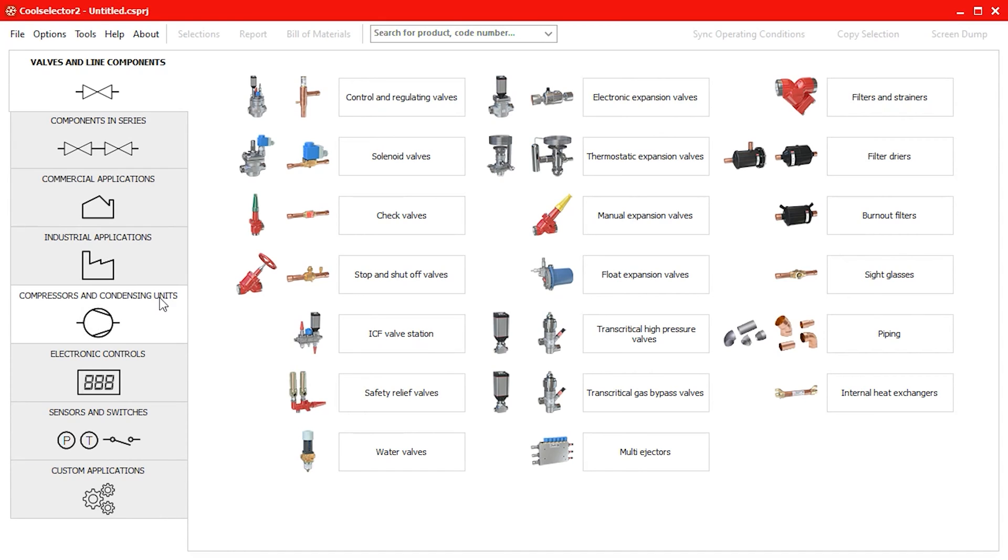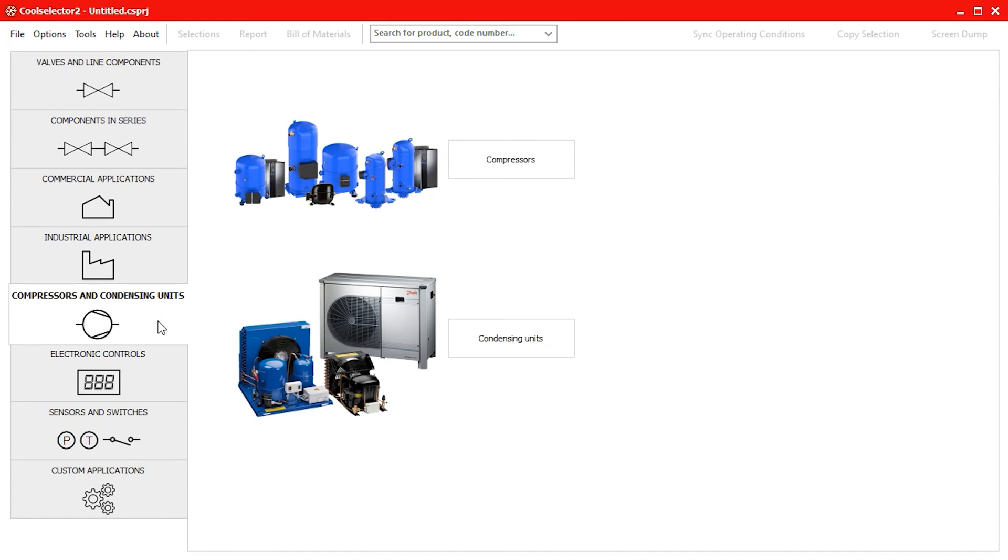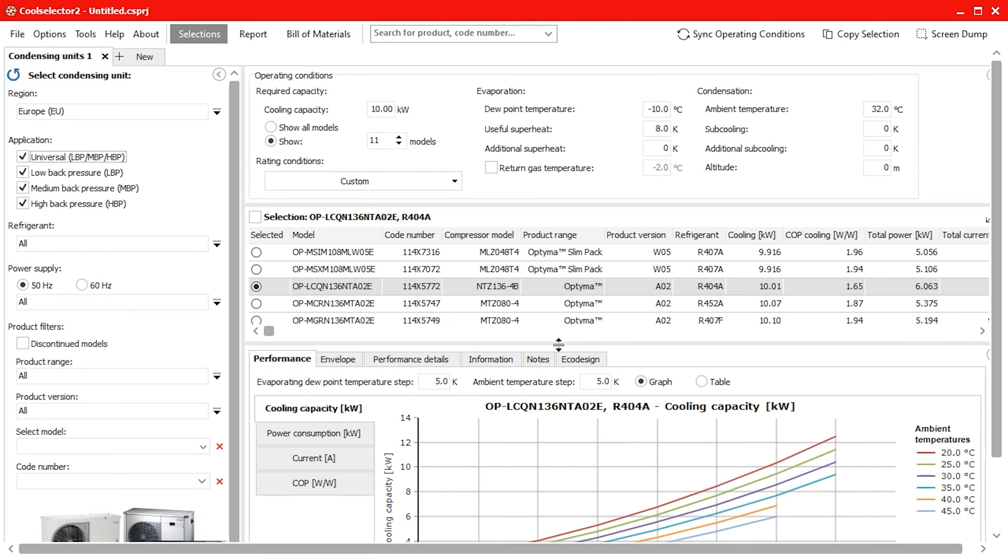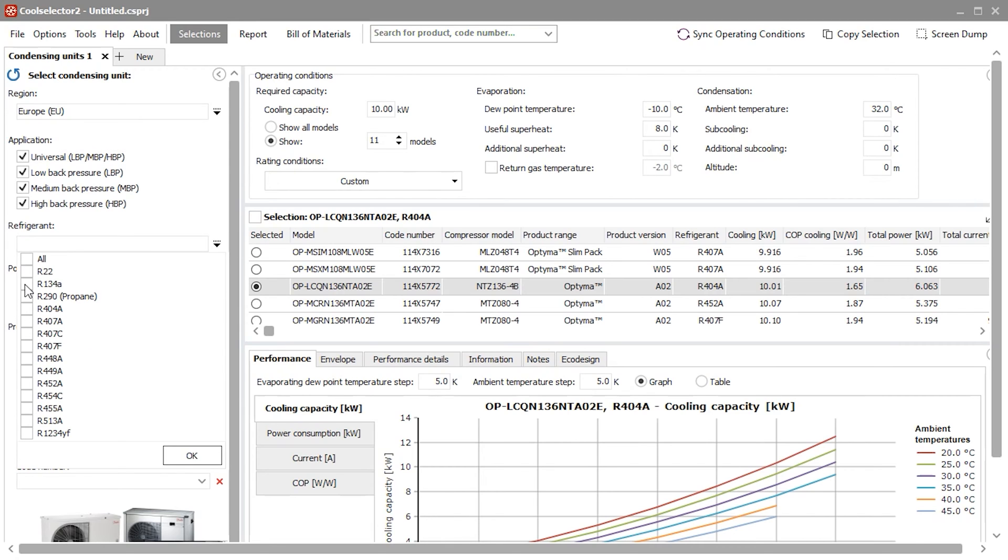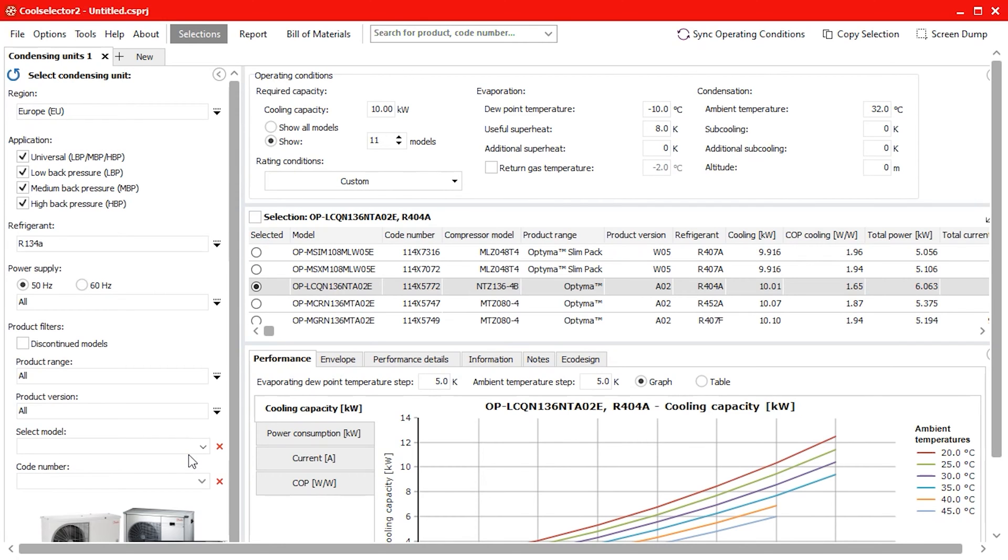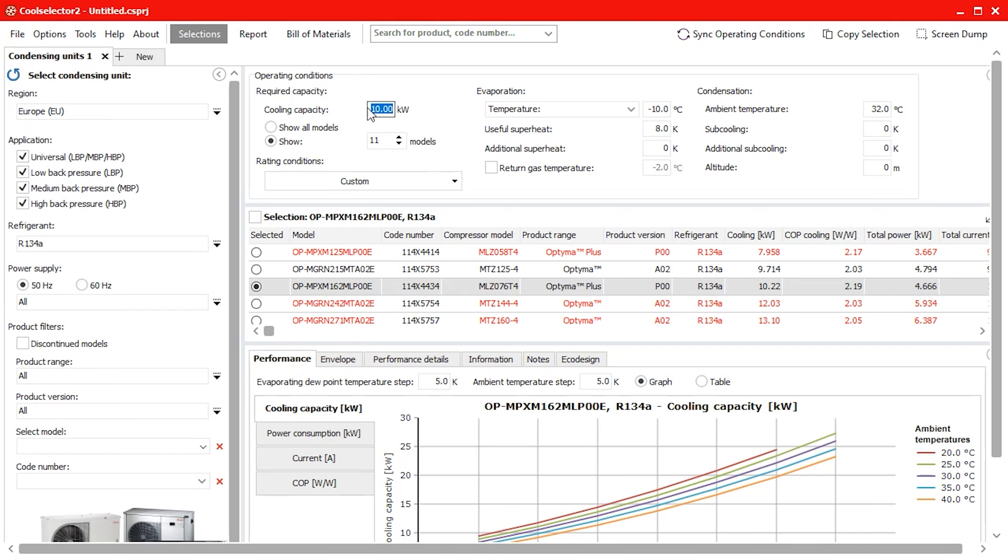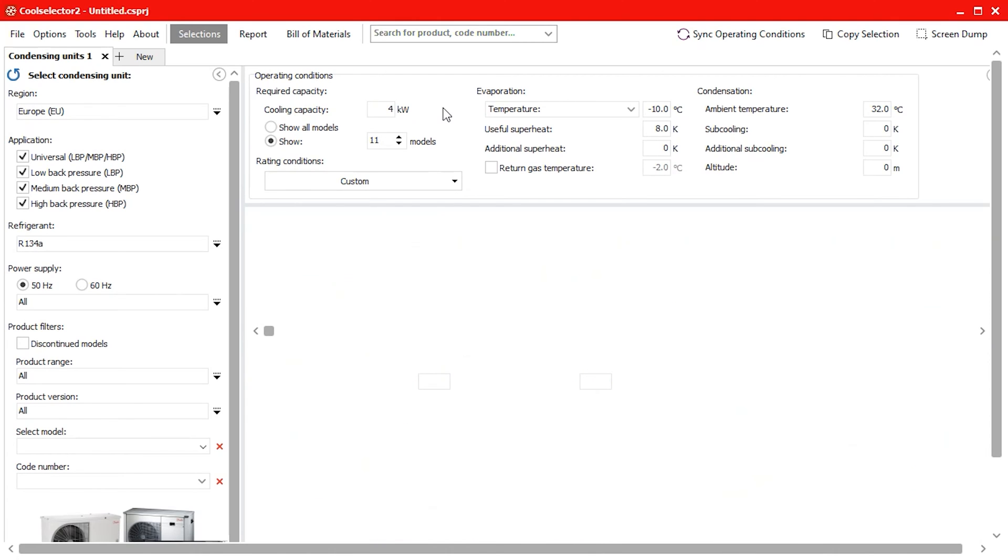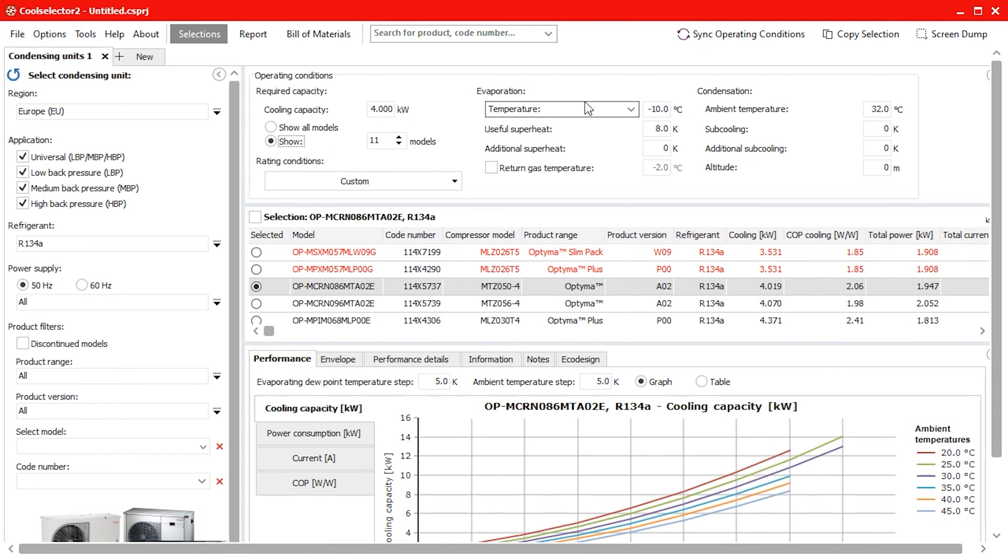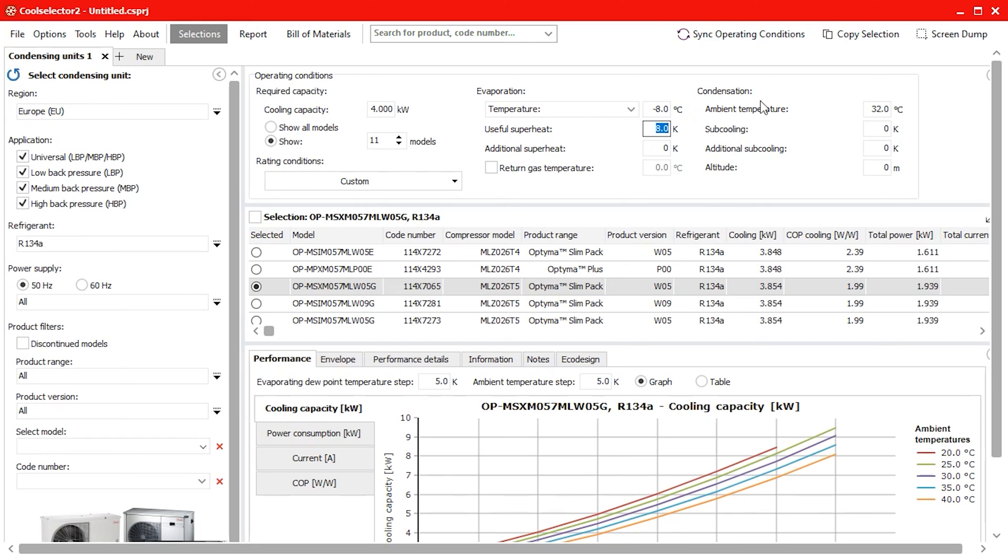We will head to the compressors and condensing unit option and then select condensing units. We will select refrigerant R134A from the drop-down options and then define the operating conditions as 4kW of cooling capacity, an evaporation temperature of negative 8 degrees Celsius, an ambient temperature of 32 degrees Celsius with 2K of sub-cooling.